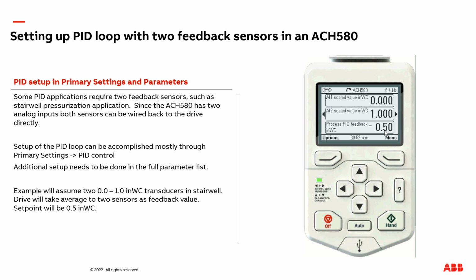Now, what I'll do is I'm going to adjust analog input 1 to be a 1/2 inch of water column, and let's verify that now my process feedback goes to 0.75 inches of water column. Good. It's a good idea to always make sure you check your process feedback is accurate and ranging correctly after you set up your PID loop.